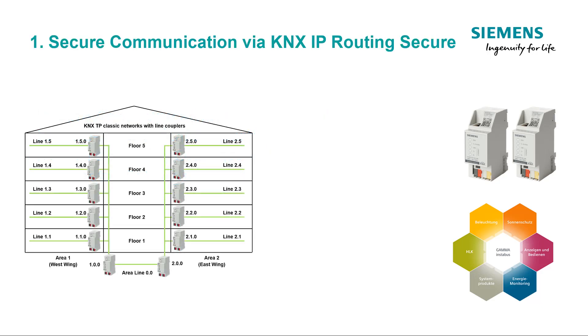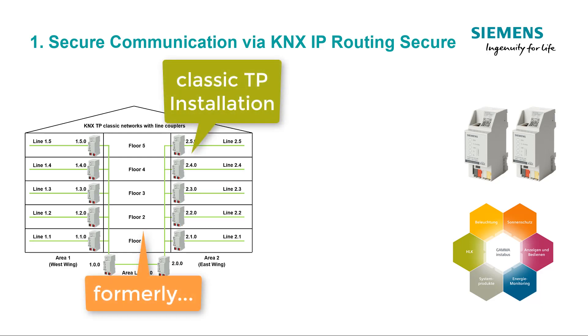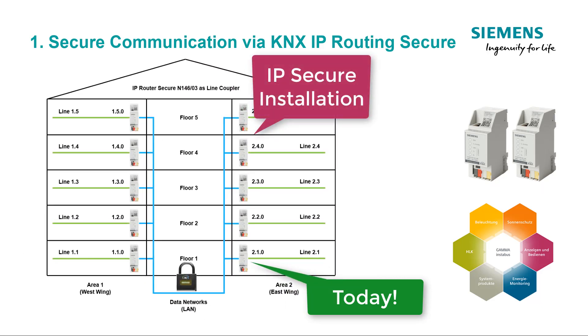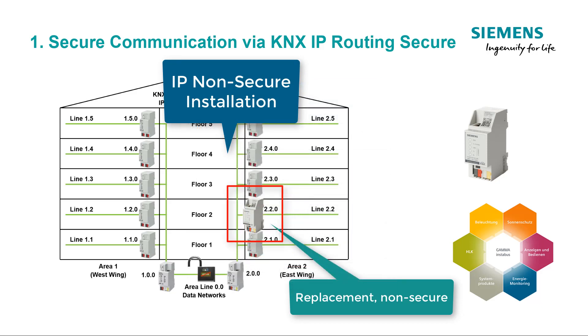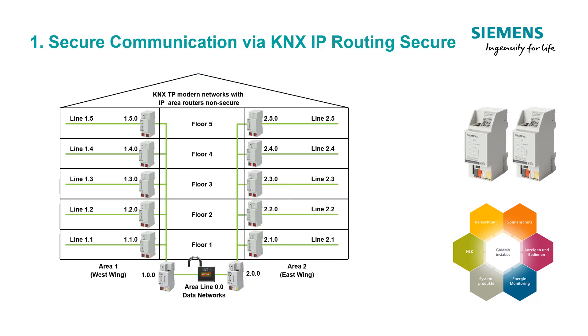Secure Communication via KNX IP Routing Secure. The Siemens KNX IP Secure products use the described procedure KNX IP Secure. Like its predecessors, the IP Router Secure N146/03 can be used instead of twisted pair, line or area couplers, and uses the KNX IP Routing Secure method. This secure transmission method can optionally be deactivated in ETS, meaning this product can also be used in existing systems with older, non-secure IP routers as an expansion or replacement device.